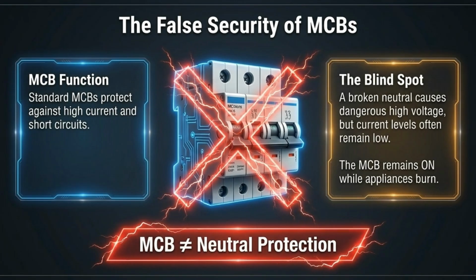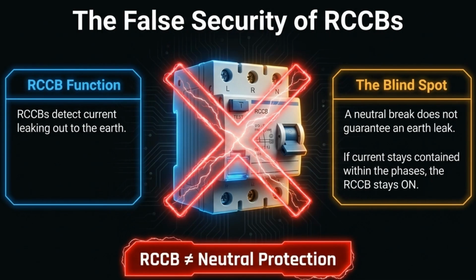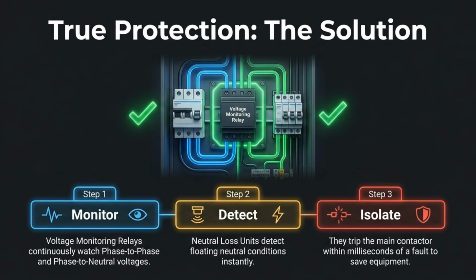It is critical to remember that standard circuit breakers, or MCBs, are not designed to protect against this. They respond to high current, which may not occur during a neutral break. Similarly, residual current circuit breakers, or RCCBs, are not a solution. They look for leakage to the earth, but a neutral break often keeps current contained within the phases. The true solution is a voltage monitoring relay. These devices monitor phase voltages and can instantly isolate the system if a floating neutral condition is detected.